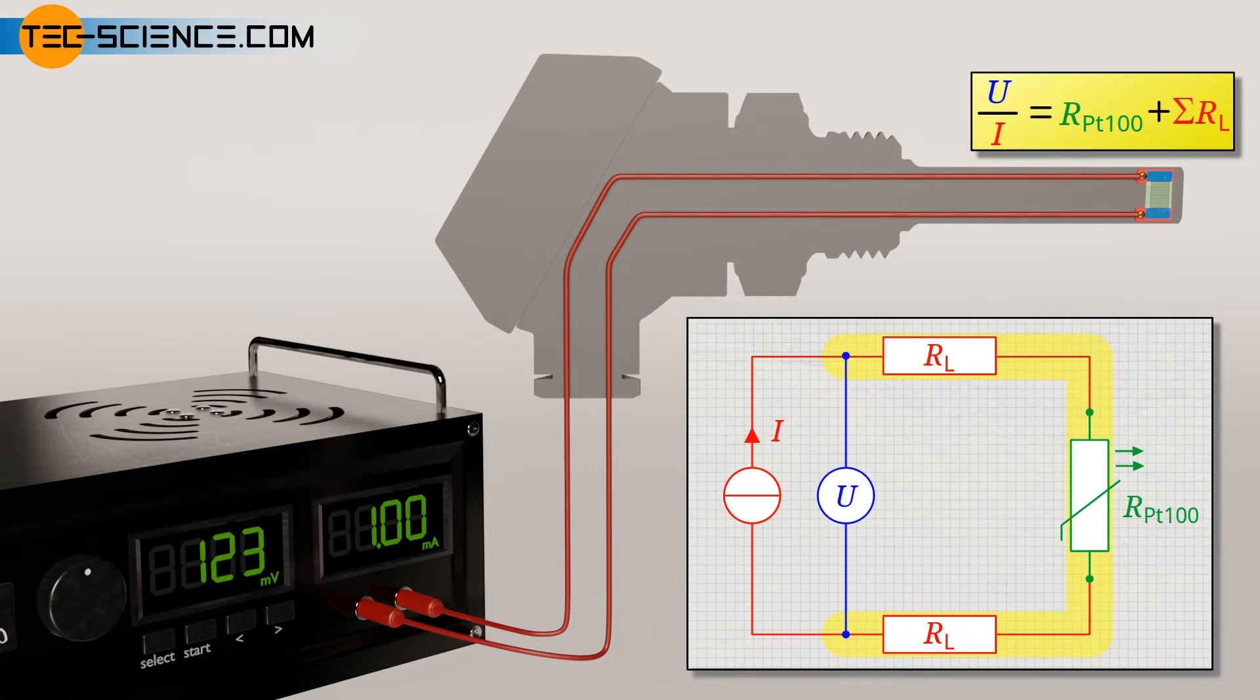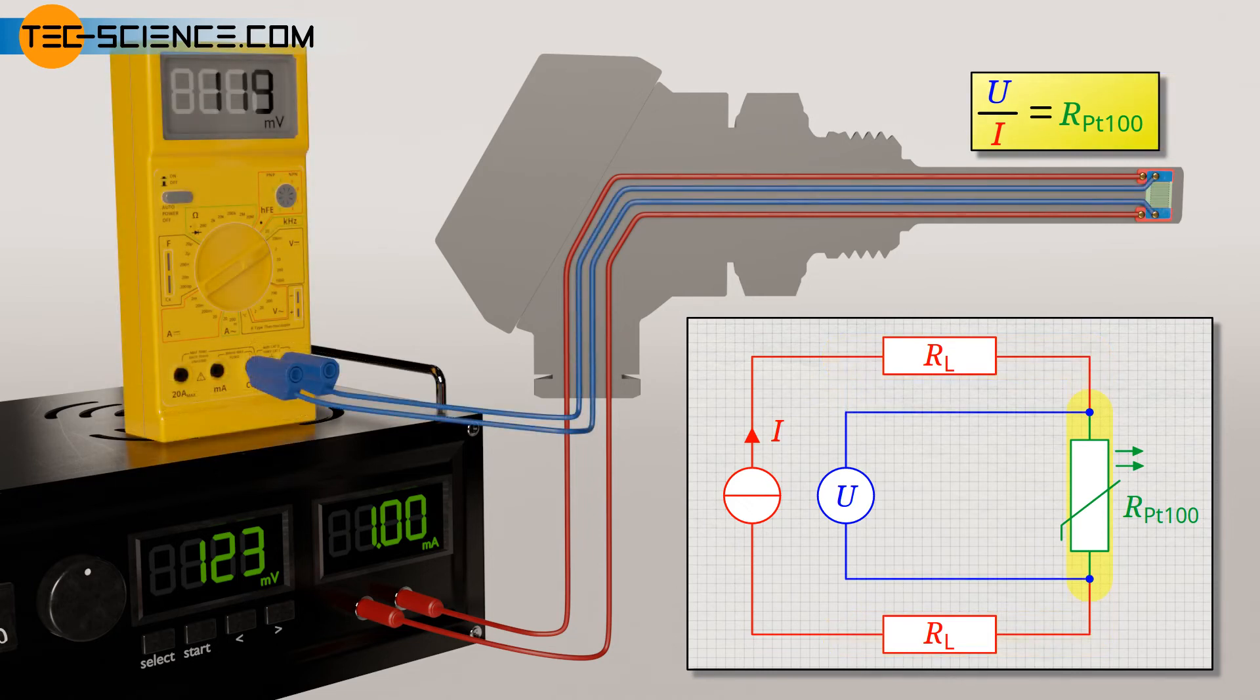The lead resistances can be compensated by four-wire sensing, which is then called four-terminal sensing. In this case, the current source and voltage measurement are separated from each other. This means that the voltage is no longer measured directly at the current source, where voltages across the leads would also be measured, but directly at the sensing resistor. This means that four wires are required. Two for the power supply to generate the constant current and two more for measuring the voltage. With the known constant current of the power supply unit and the measured voltage directly across the PT100, the resistance can now be determined from Ohm's law without lead resistances influencing the result.